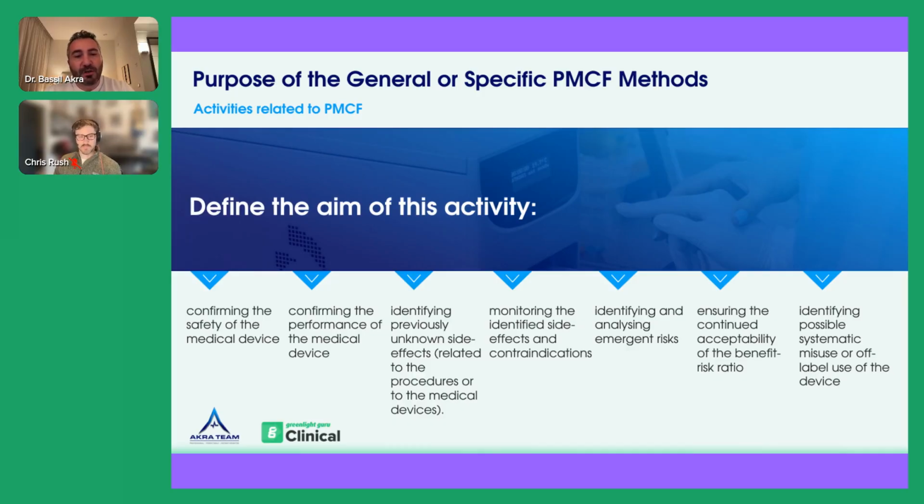And it's not always required to have a study. You might have a registry, you might have prospective, retrospective data analysis. You might have a combination of multiple methods. And for some devices, you might justify, for that device design, I have enough data that I don't need to collect new data. And then you'd focus just on reviewing the literature till you do any significant change to the design or you get any signal from the market, then you reevaluate again, do I need a specific PMCF?